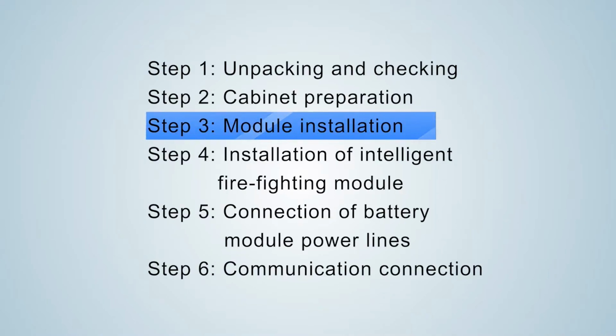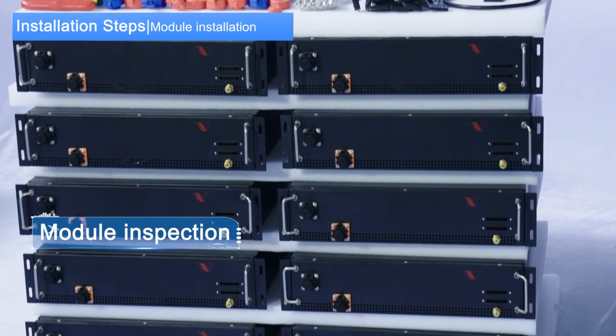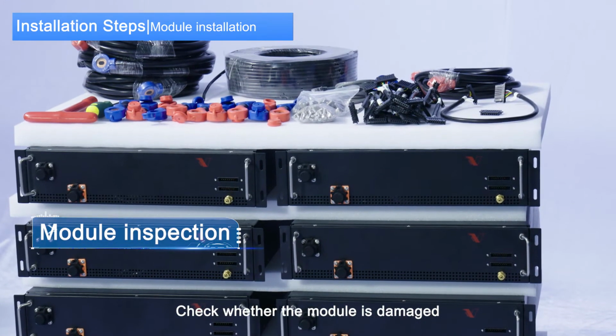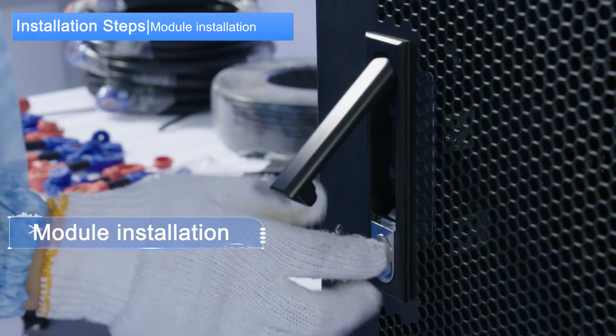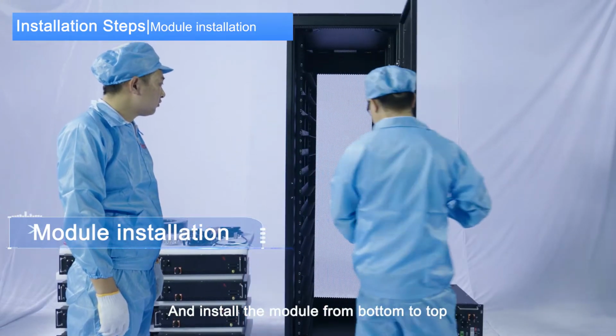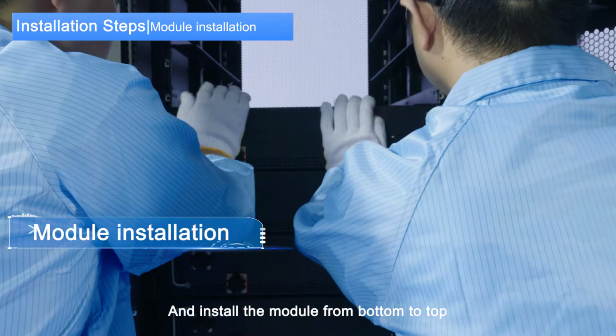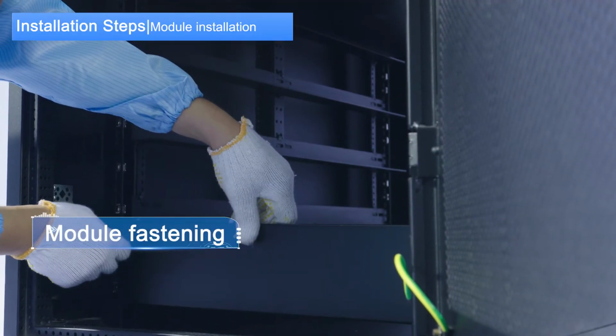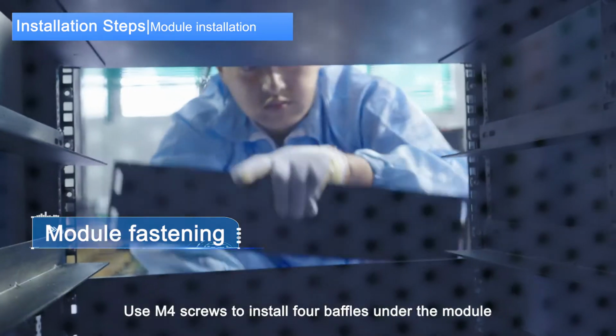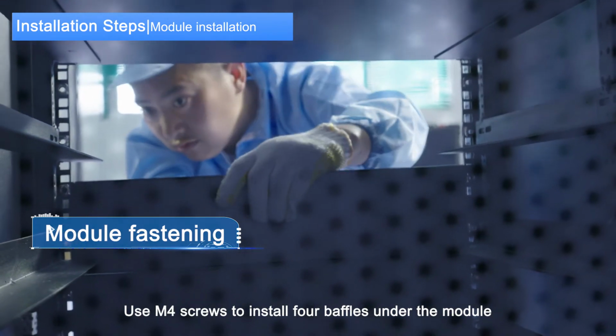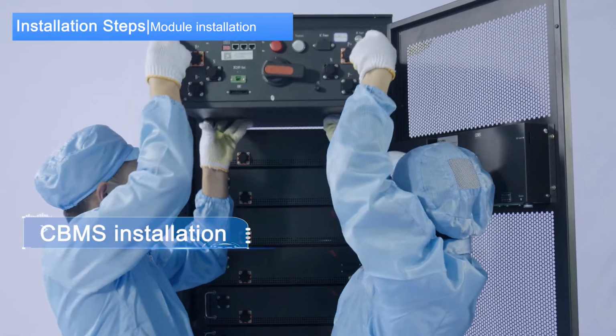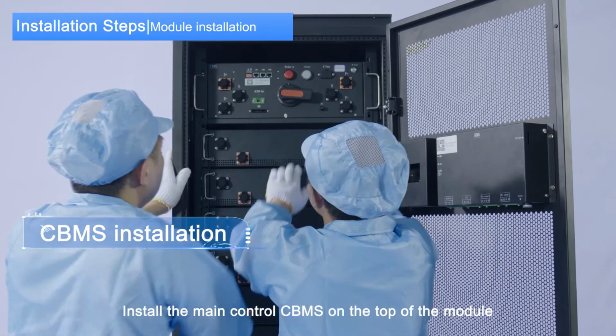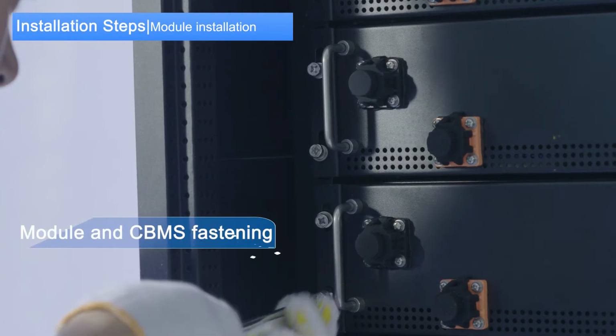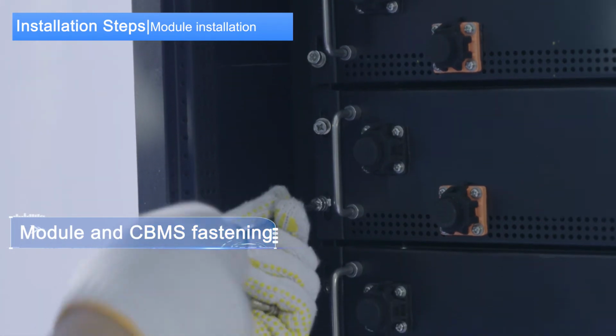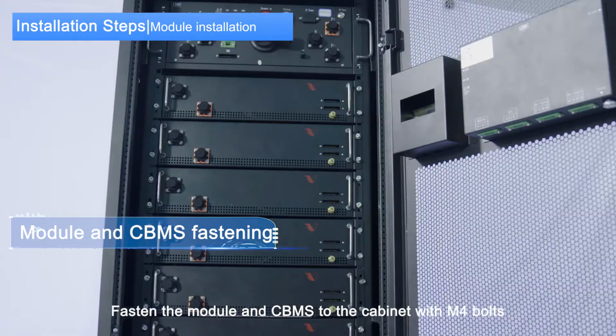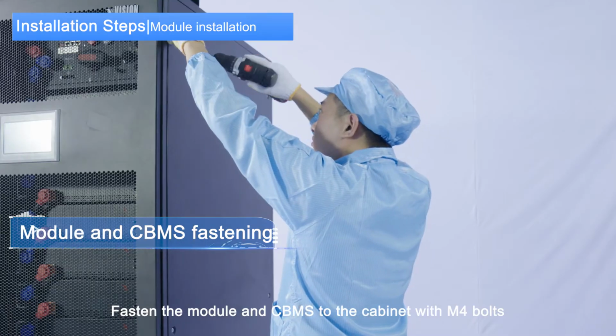Step 3. Module installation. 1. Module inspection. Check whether the module is damaged. 2. Module installation. Open the cabinet door and install the module from bottom to top. 3. Module fastening. Use M4 screws to install 4 baffles under the module. 4. CBMS installation. Install the main control CBMS on the top of the module. 5. Module and CBMS fastening. Fasten the module and the CBMS to the cabinet with M4 bolts.